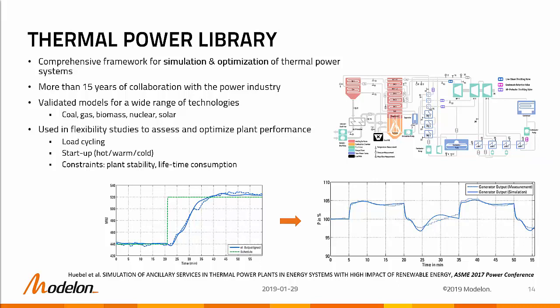This was done to assess flexibility of the plant and to optimize it, typically during load cycling, when you ramp the power plant up and down, or during startup. When you optimize plant performance, you want to still maintain overall plant stability, keeping temperatures and pressures within reasonable ranges, and you want to minimize the lifetime consumption of critical components in the steam cycle exposed to high thermal and mechanical stress during those transients.